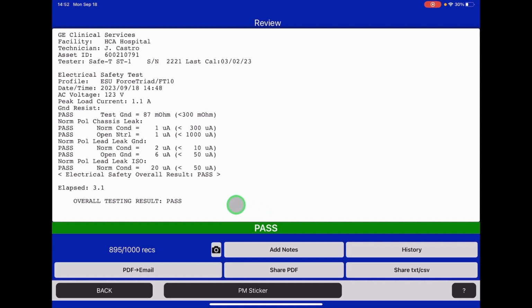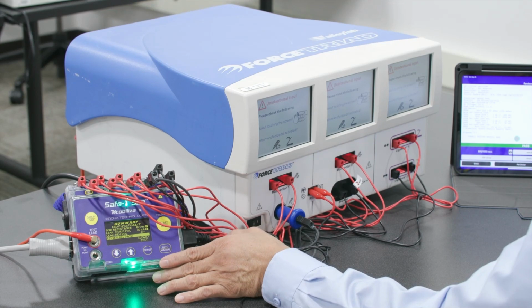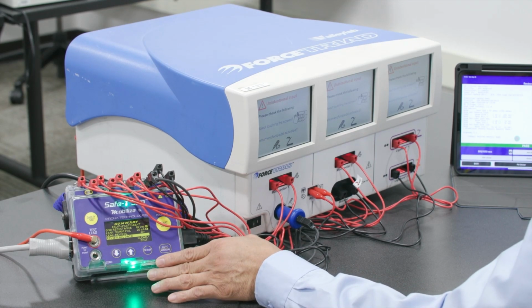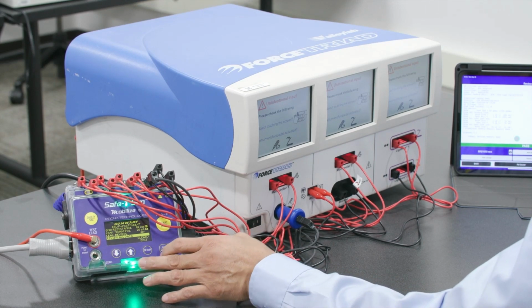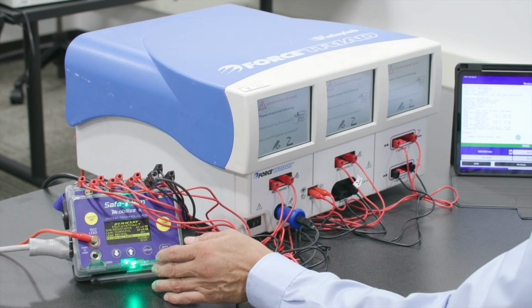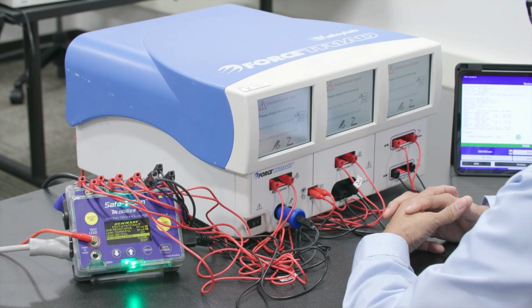And the same thing on the safety analyzer itself. You can see the safety analyzer is glowing green, letting you know every test passed. If anything failed, the analyzer would also be red. So we've completed the test for this ForceTriad device.